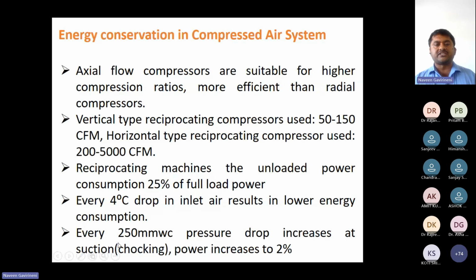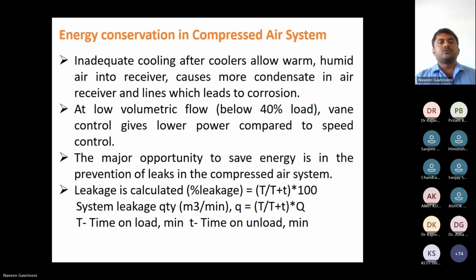This is also one of the most important energy conservation points. For every 250 mm of water column pressure drop increase in suction, power increases by 2%. Inadequate cooling also plays a vital role. For a low volume flow, when the load is less than 40%, it is advisable to go for vane control, not speed control. Why? Because speed control will take more power. The major opportunity to save is leak prevention, as I explained.